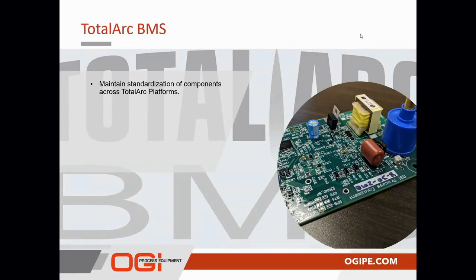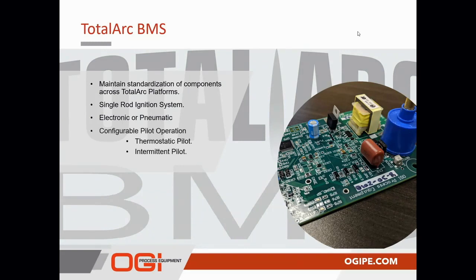A single ignition rod, just as it is for the TotalArc, is used for both flame ignition and sensing. The TotalArc BMS is fully adaptable to operate in either a pneumatic or a fully electronic control environment. Operation can be configured in any of 3 ways, but I've only shown 2 here. A thermostatic pilot, which can also be configured to be a standing pilot, or an intermittent pilot.